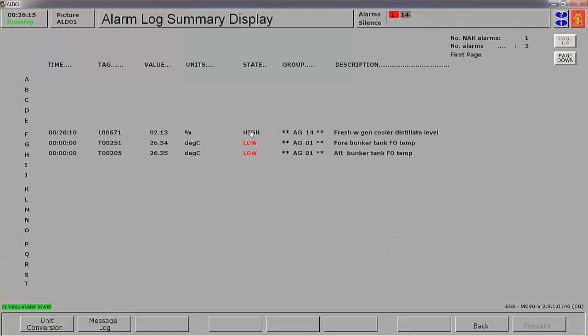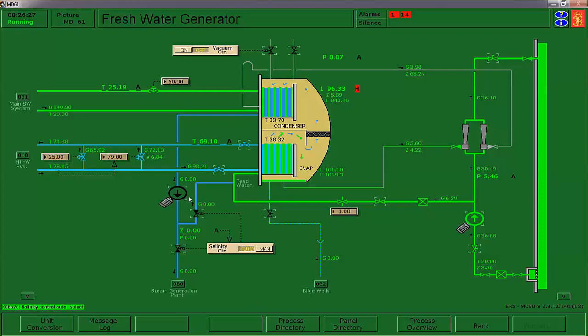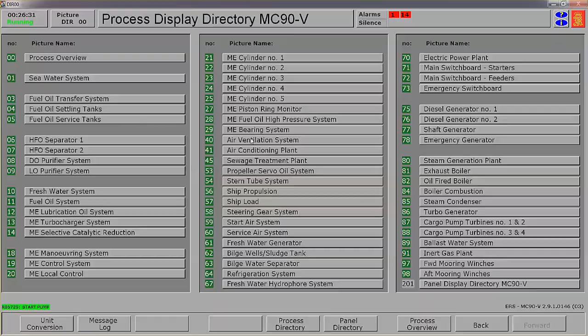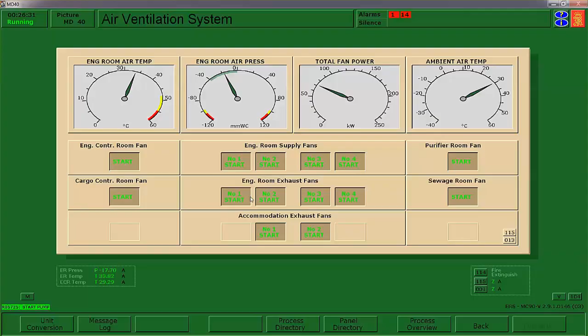All right. So my distillate condenser, I forgot to go back and check. It's overflowing now, so let's do that. Freshwater generator, it's not a big deal. It gets pulled out with the brine. Put your salinity control in auto, and go ahead and put your distillate. At this point too, I'm going to check my ventilation. We're starting to go into a vacuum, so I'm going to shut down both of my exhaust fans.